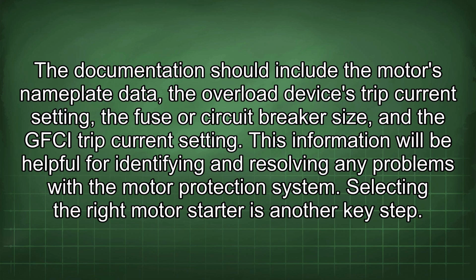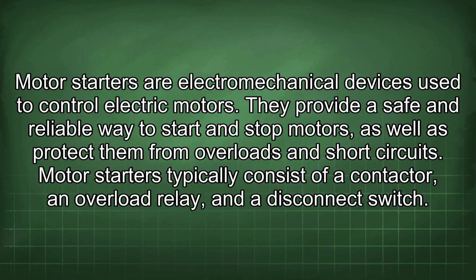Selecting the right motor starter is another key step. Motor starters are electromechanical devices used to control electric motors. They provide a safe and reliable way to start and stop motors, as well as protect them from overloads and short circuits. Motor starters typically consist of a contactor, an overload relay, and a disconnect switch.